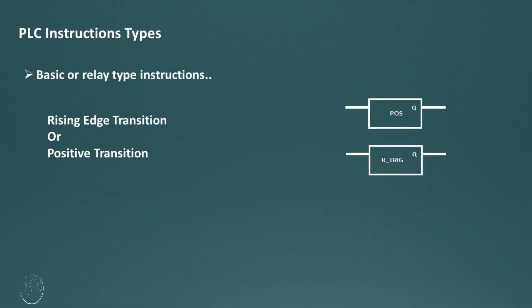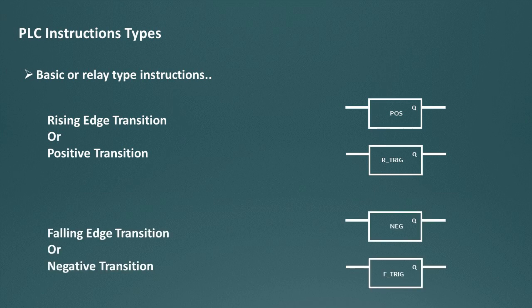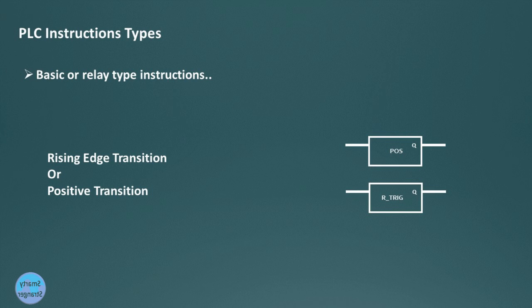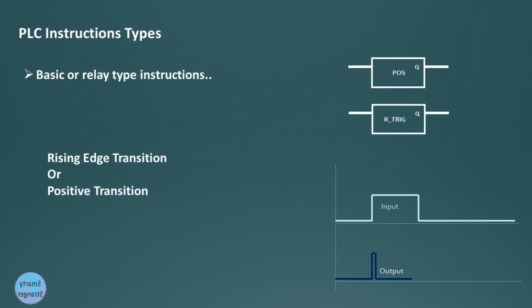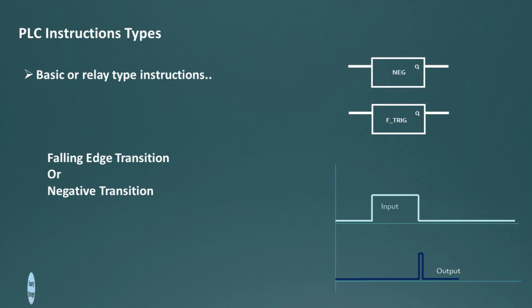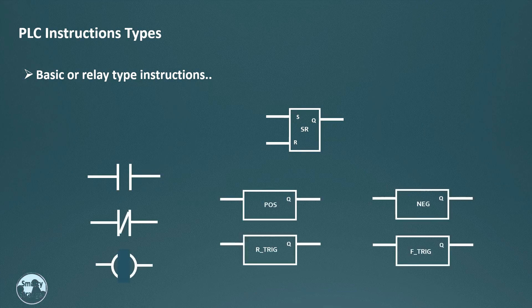Now let's look at positive or rising edge detection instructions and negative transition or falling edge detection instructions. Different PLCs use different names for these instructions. Their working concept is roughly the same. The positive transition instruction detects the positive transition of an input signal — a state change from low to high — and gives a high output for one cycle. The negative transition instruction detects a signal change from high to low and also gives a high output for one cycle.